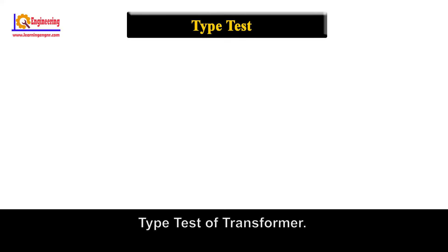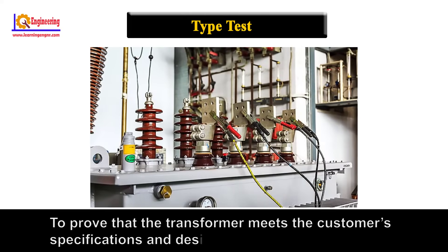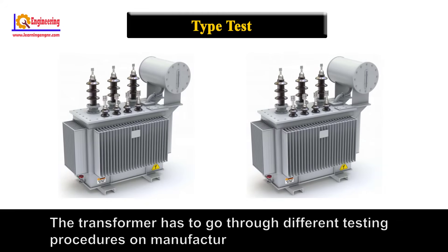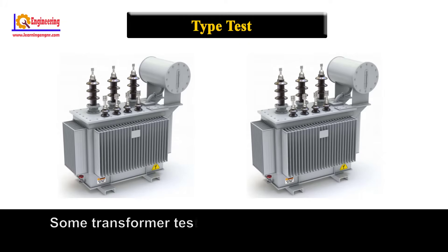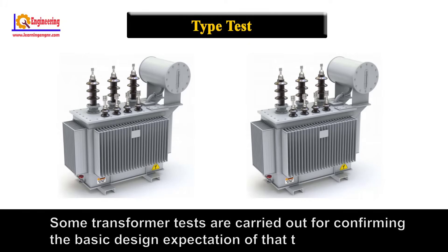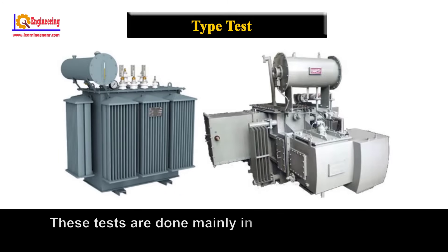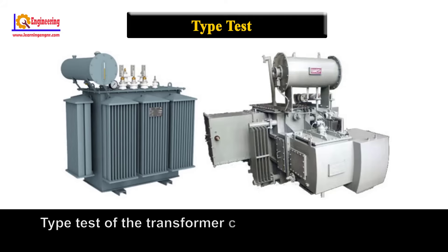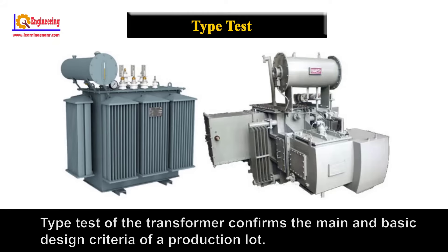To prove that the transformer meets the customer's specifications and design expectations, the transformer has to go through different testing procedures on manufacturer premises. Some transformer tests are carried out for confirming the basic design expectation of the transformer. These tests are done merely on a prototype unit, not on all manufactured units in a lot. Type test of the transformer confirms the main and basic design criteria of a production lot.